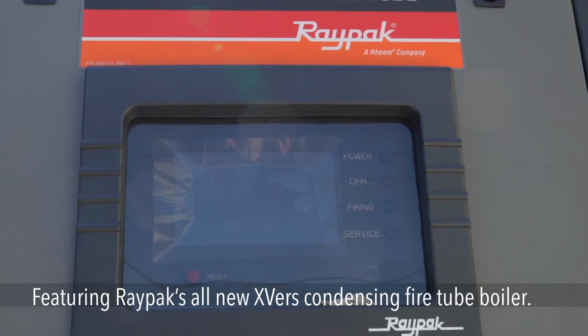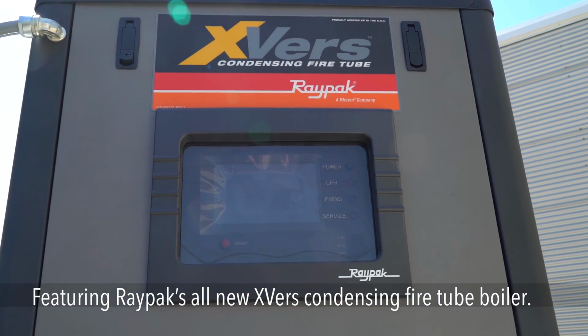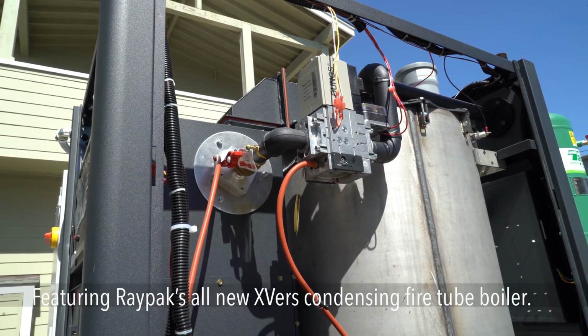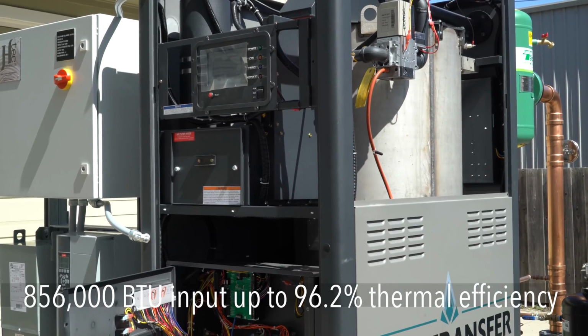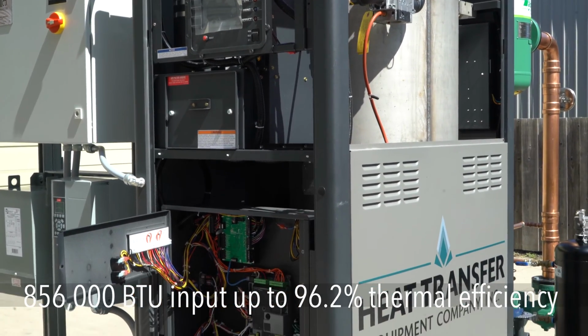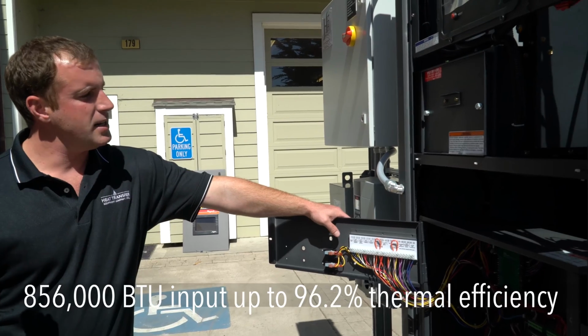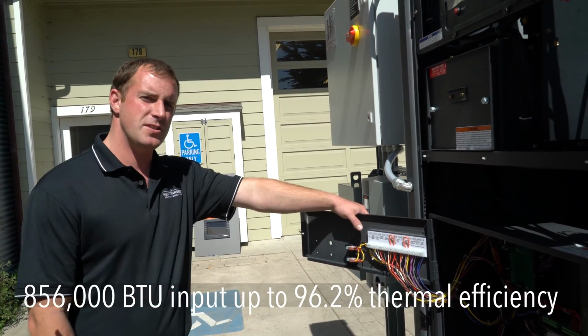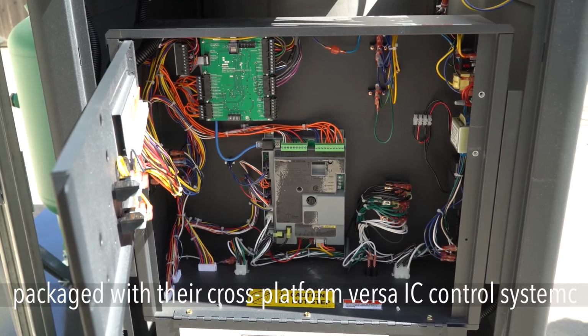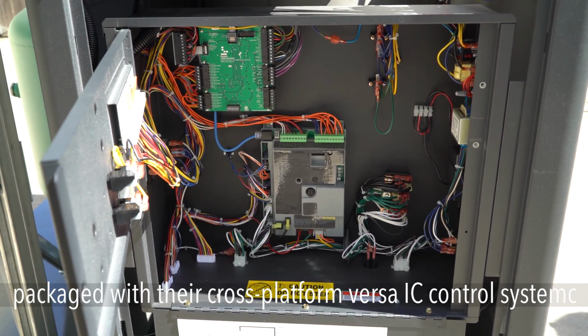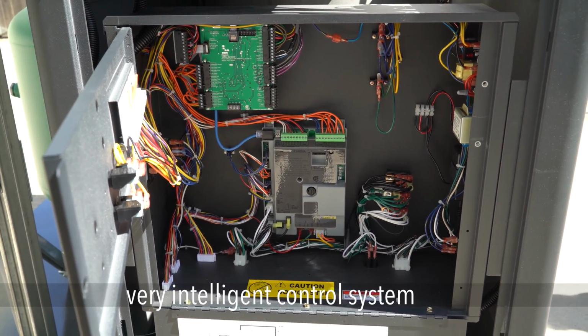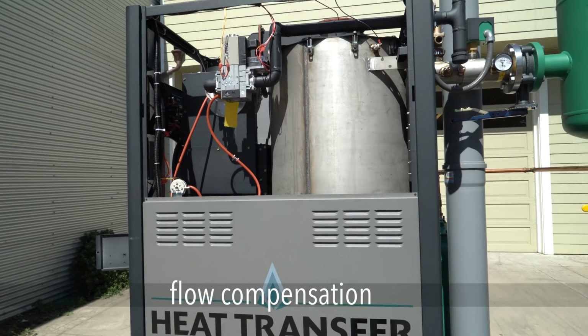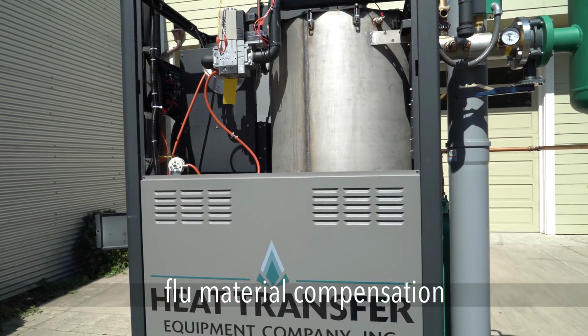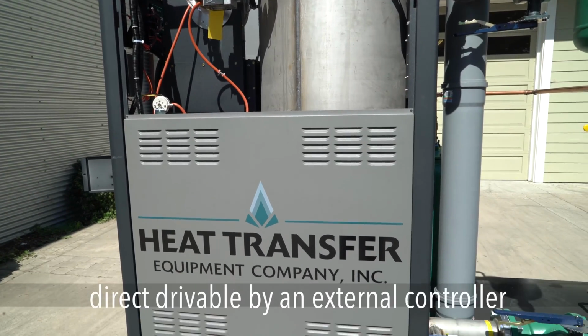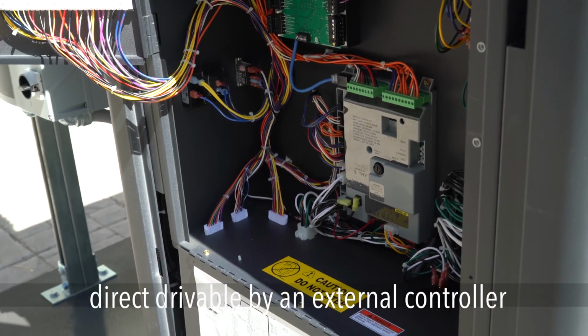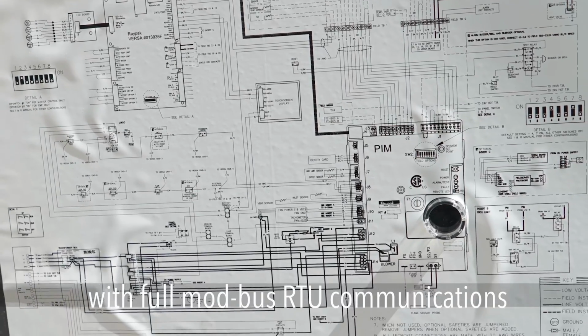Equipped with Raypak's all-new XVers outdoor-rated, fully condensing stainless steel fire tube boiler. This particular model is their smallest model, 856,000 BTU input, up to 96.2% thermal efficiency at full fire. Packaged with their cross-platform Versa IC control system. Very intelligent control system: glycol percentage, flow compensation, flue material compensation. Also cascadable, direct drivable by an external controller with full Modbus RTU communications.